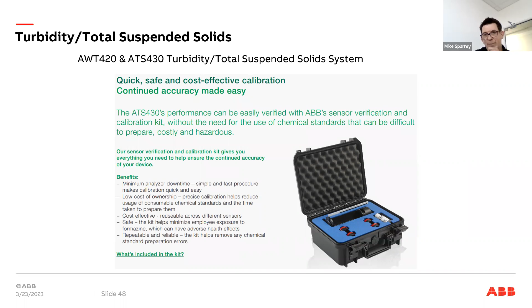And to support the ongoing maintenance of the sensor, we provide calibration kits. These are using Perspex calibration pucks. We do a high and a low puck, and we do it for two ranges, so you can cover the measurement ranges within the application. You select which pair of pucks you would use, depending on whether it was a final effluent or ASP lanes.